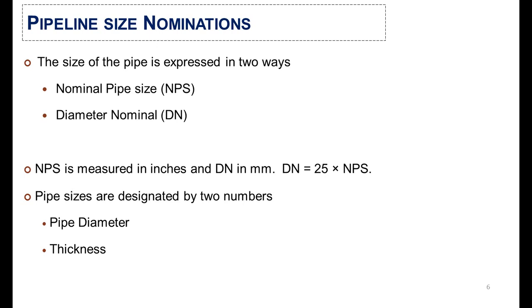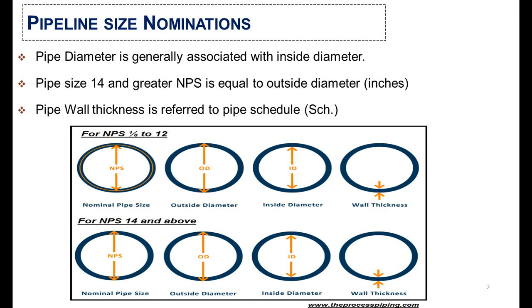The size of the pipe is expressed in two ways: first is Nominal Pipe Size (NPS), and second is Diameter Nominal (DN). NPS is measured in inches and DN in millimeters, and both are interconvertible. Pipe size is designated by two numbers: pipe diameter and thickness. Pipe diameter is generally associated with inside diameter. For pipe size 14 NPS and greater, NPS equals outside diameter. Pipe wall thickness is referred to as the pipe schedule.